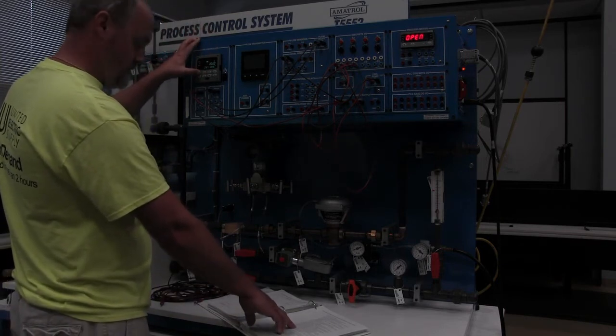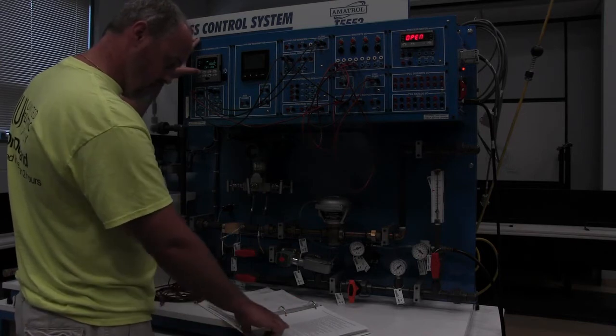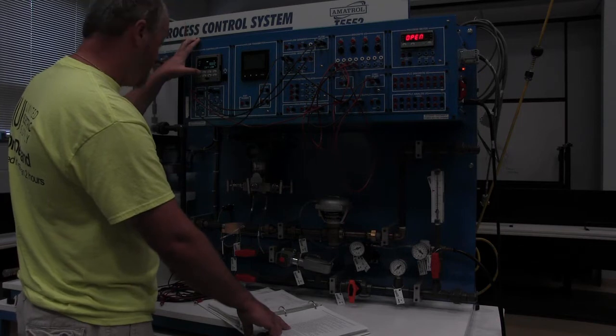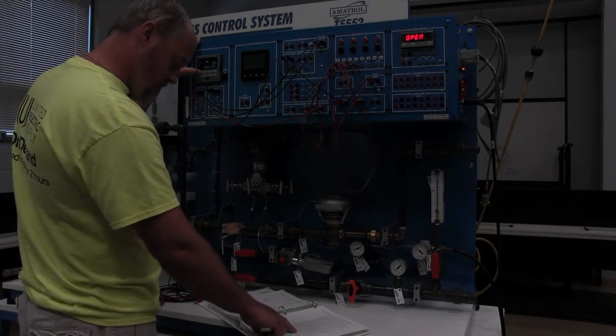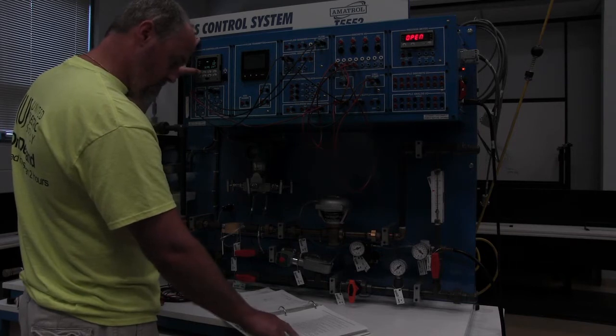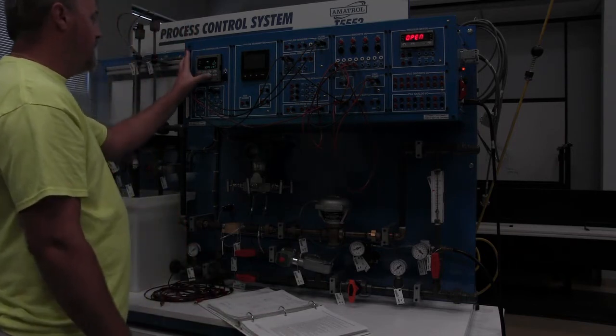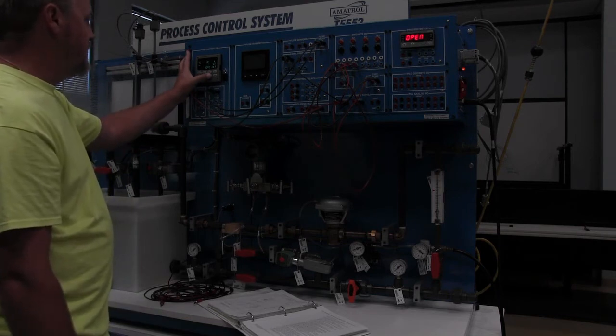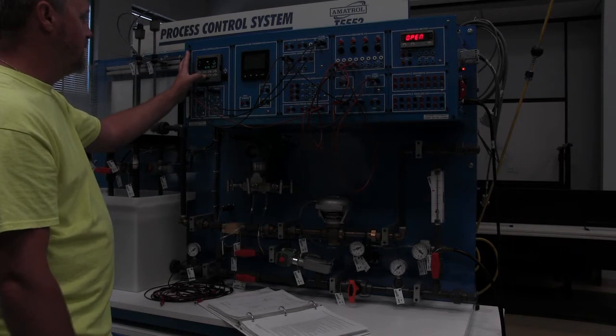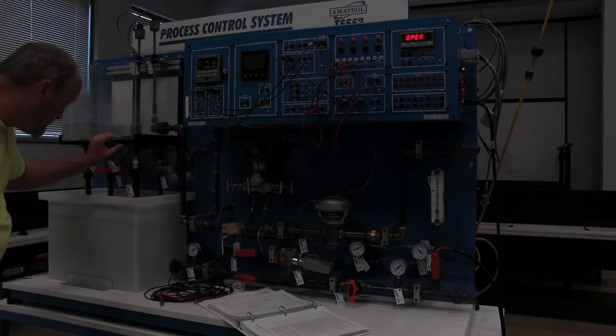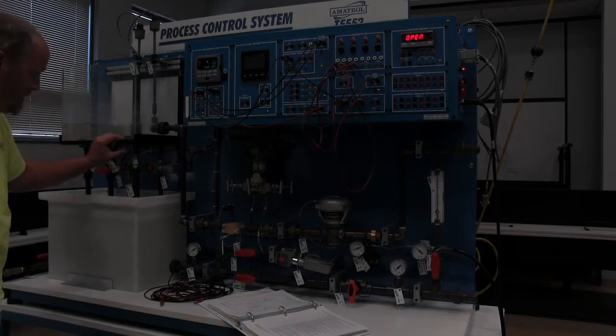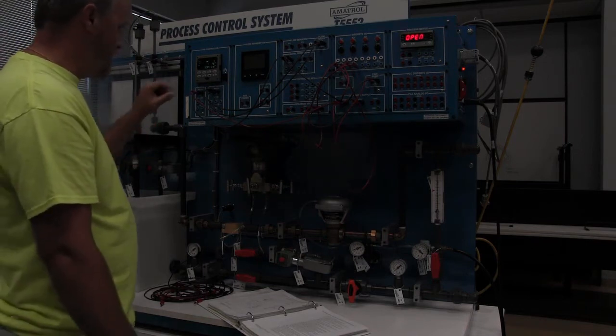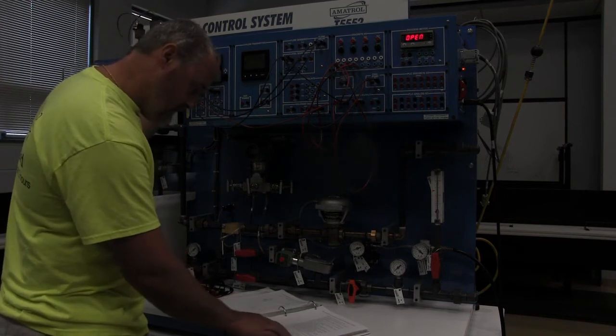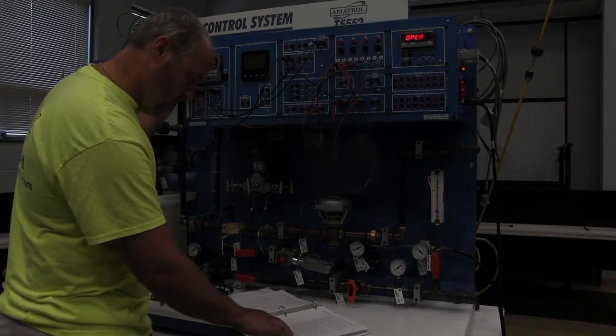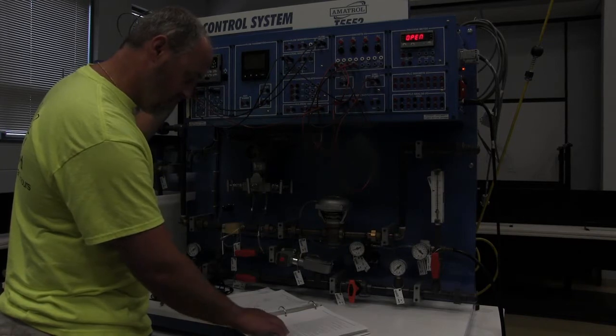We're going to go to low. Low we want to be 0, which it currently is. And then we want to go to bias in. Bias in, we want to be negative 4.1. I don't think 4.1 is correct, but we're going to find out. This is setting the offset because where this pressure transmitter is, there's a bulkhead fitting in there, and there's a little bit of level in it previously, so you have to offset it just a little bit. It says there's approximately 4.1 inch offset between the tank and the 0 reading.